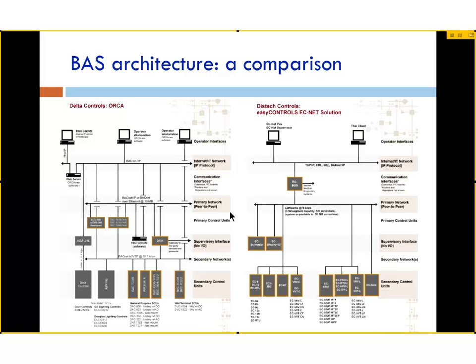But if you look closely, I don't know if you can see it, it may be kind of small, but you have the primary internet protocol, TCP/IP level, where you see on the Delta Controls, they use BACnet, which is the Building Automation and Control Networks communications protocol, which was initially developed by ASHRAE and is now an ANSI and ISO standard. That is very prevalent in the industry. It can communicate over various types of media, and it has 50 standardized objects, where if you're BACnet compliant in Delta Controls, you would have the same 50 objects that you would have, let's say, in a Distech control system that's also BACnet compliant. So when you get to that level right there, you can pass packets right across the internet.